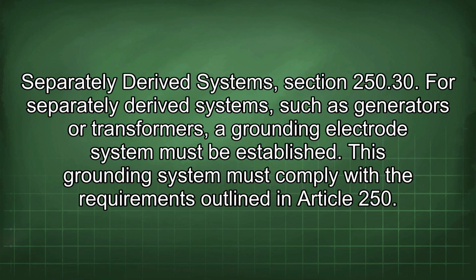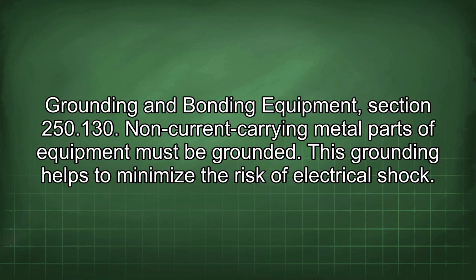Separately derived systems, section 250.30. For separately derived systems, such as generators or transformers, a grounding electrode system must be established. This grounding system must comply with the requirements outlined in Article 250. Grounding and bonding equipment, section 250.130. Non-current carrying metal parts of equipment must be grounded. This grounding helps to minimize the risk of electrical shock.